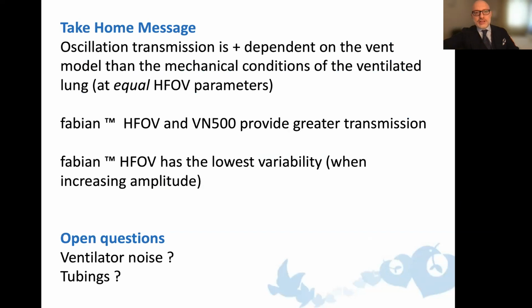So as a take-home message, I will tell you that the oscillation transmission is more dependent on the ventilator model than on the mechanical condition of the lung being ventilated, although this must be considered, obviously, at equal HFOV parameters. And you gotta know what are the boundaries to be preferred or that can be used in each machine according to the data coming from the other studies that I showed you. You gotta know that Fabian HFO and VN500 provide the greater transmission overall, and the Fabian HFO has the lowest variability, so the more steady oscillation transmission when you are increasing amplitude, which is something that we do at the bedside every day.